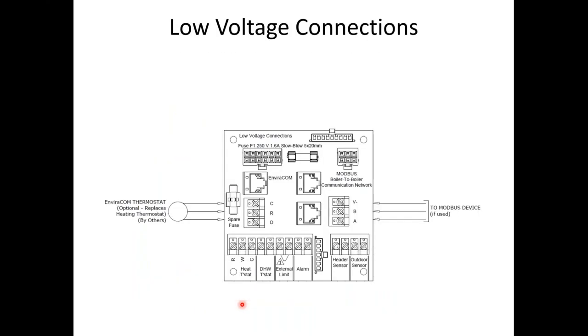Your low voltage connections are going to be fuse protected. There is a common for using a 3-wire thermostat, such as the Nest, the Ecobee, or the Lyric. One of the common mistakes I've made wiring these is I tend to wire the common and the aquastat together, and I instantly pop that low voltage fuse. So if you go to first turn the boiler on and give it a call and energize it, and the screen goes blank and the fan runs to high speed, double check your low voltage wiring here and double check your low voltage fuse.